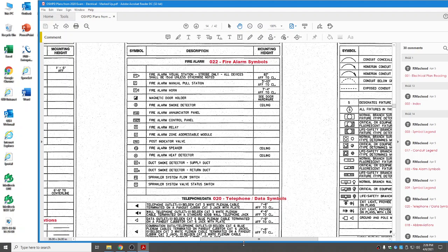Then we've got a magnetic door holder, which we'll find typically on our dual egress or cross corridor doors that are held open so that as we go through smoke compartments, we don't have doors that we have to open and close all the time. We'll put a magnetic door holder device on the wall and then open the door so that the magnet holds the door open. The moment the fire alarm goes off, it basically drops that connection. Magnet goes away and the door just goes ahead and shuts and latches, which allows our smoke compartment doors to then seal so that the smoke can't freely travel from smoke compartment to smoke compartment.